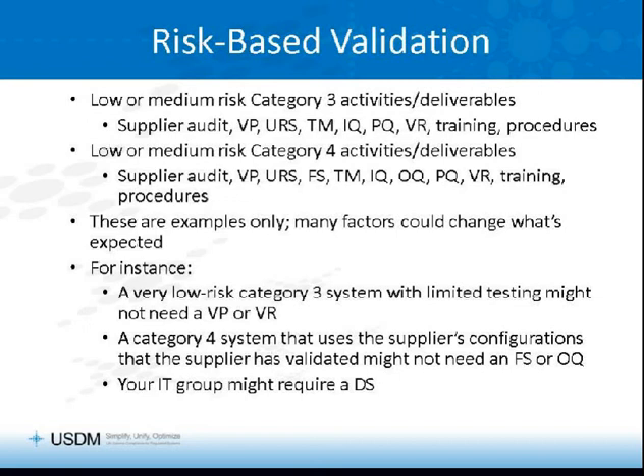With Category 3, you may get away with a lot less. Here's an example: low risk, category 3 activities or deliverables might include a validation plan, a user requirement specification, an IQ, no OQ, but a PQ to make sure it meets the user requirements, a trace matrix to tie the requirements to the testing, and a validation report.